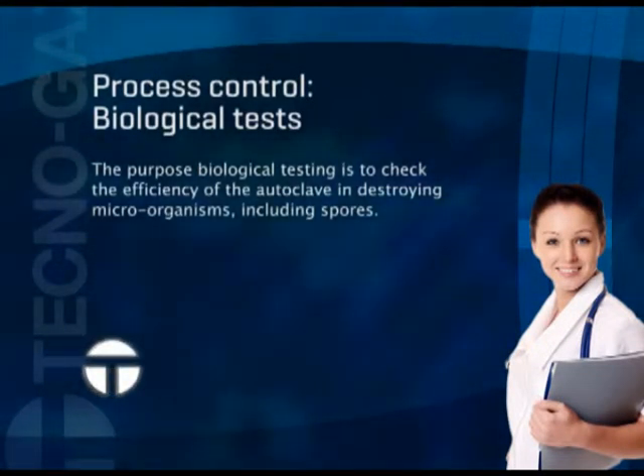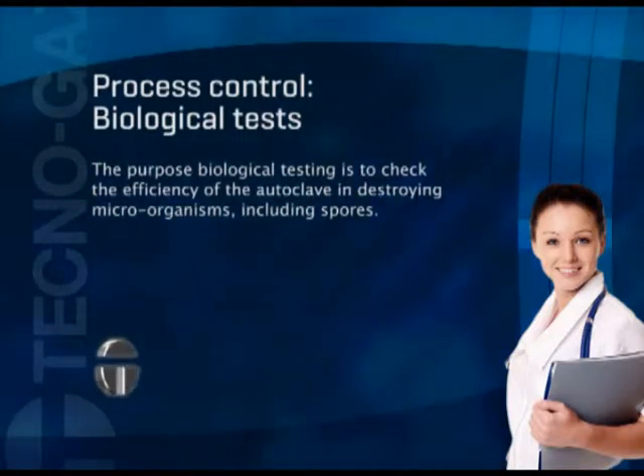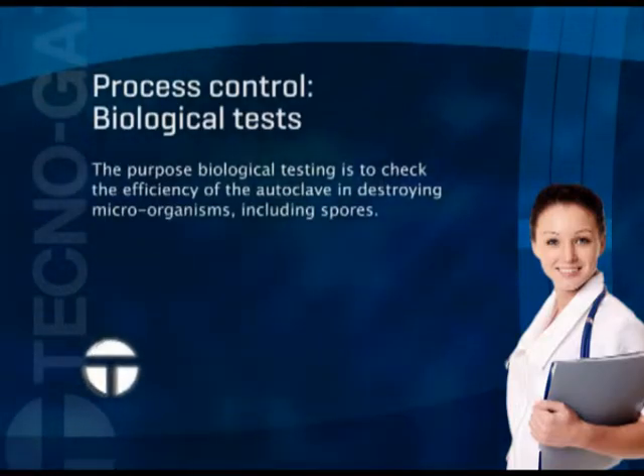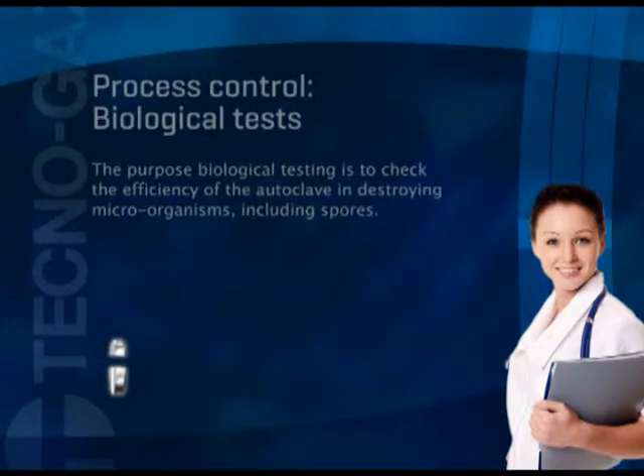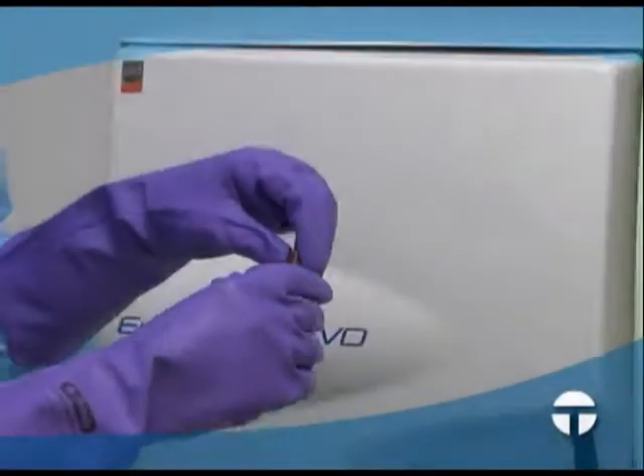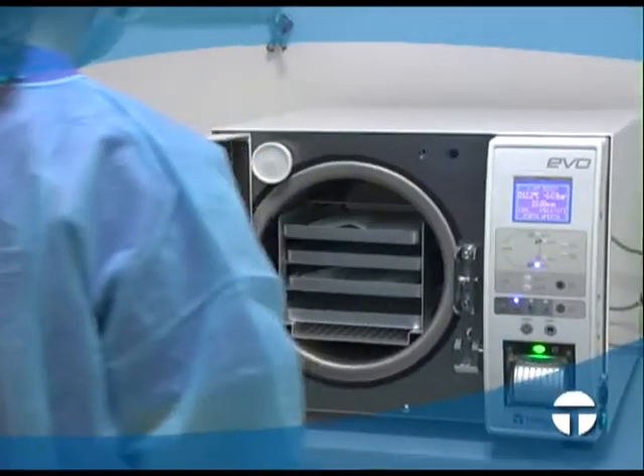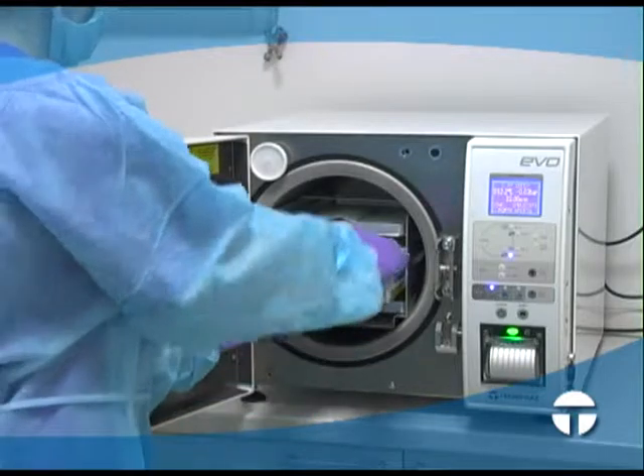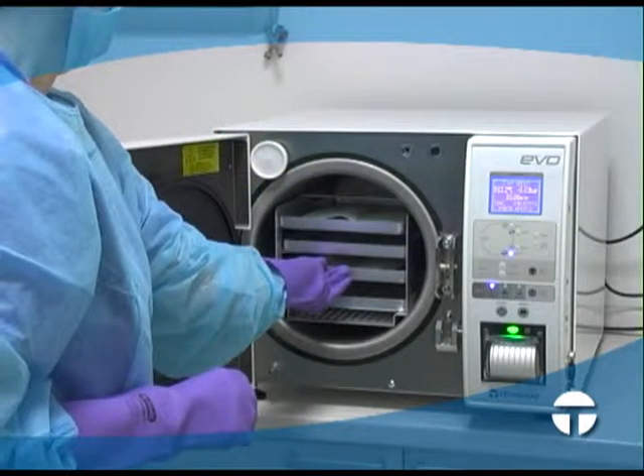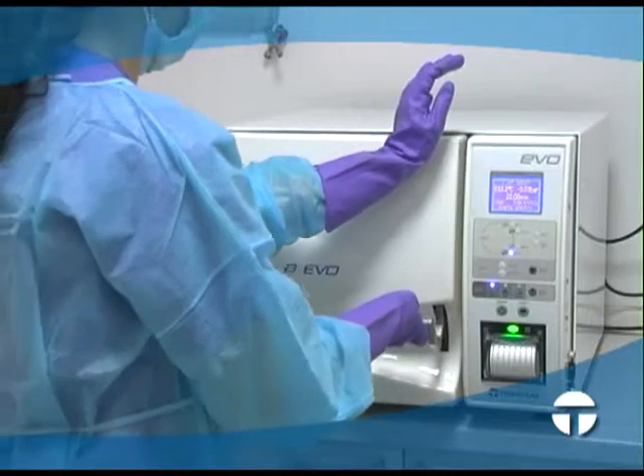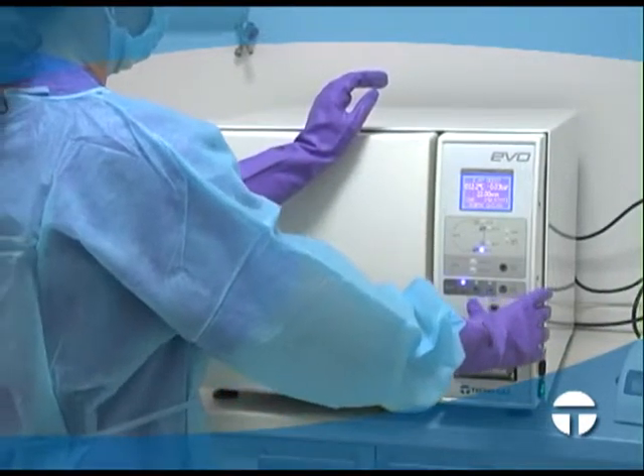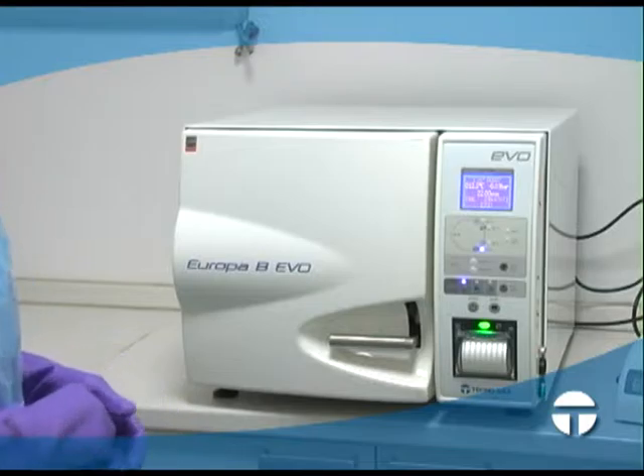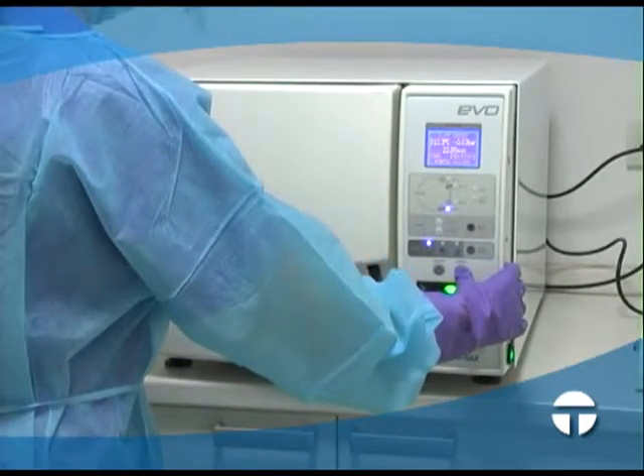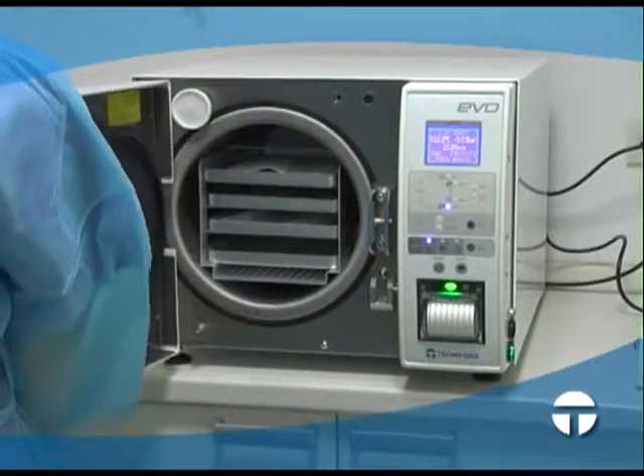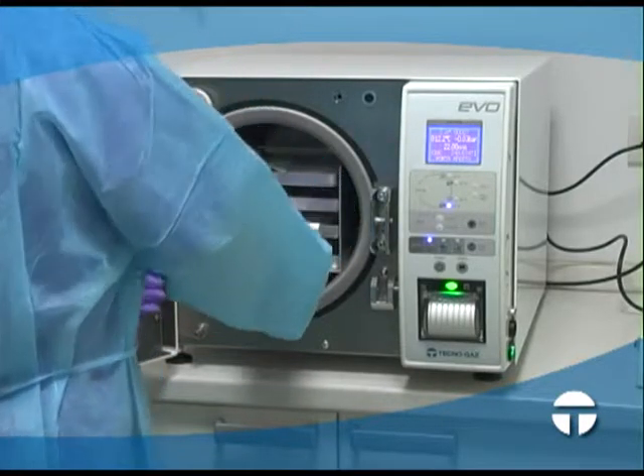Biological tests. The purpose of biological testing is to check the efficiency of the autoclave in destroying microorganisms, including spores. Place a biological test vial in the autoclave, positioning it on the central tray, which may also contain a load to be sterilized. Close the door. Select a regular sterilization cycle and start the cycle. At the end of the cycle, remove the vial.